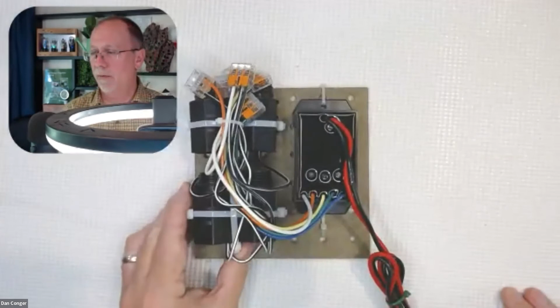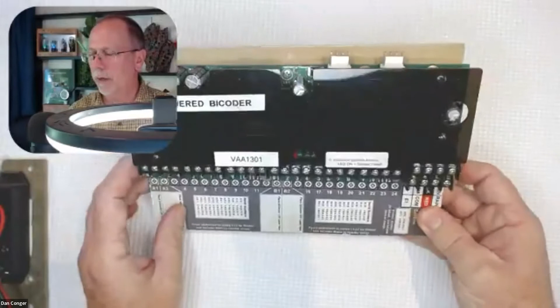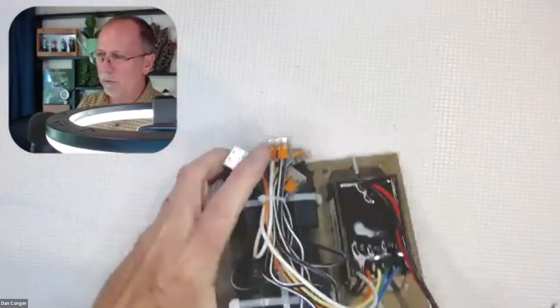Actually, there are some reasons you might use this, and they talk about it here and here. Let's say you're setting up a controller and you want to show what happens when you have a mainline break. We can set this up and not actually have a mainline break. Your mainline is designed to carry 75 GPM, so what happens when you run 150 GPM through it? Hopefully you get your alerts and it shuts down the mainline, or does whatever you told it to do. With this, you could simulate that and actually make that happen without using your flow sensor. I thought that was an interesting idea. I didn't know this existed 6 months ago, so I haven't had a chance to play with it, but it is on my list of toys to play with in my lab.